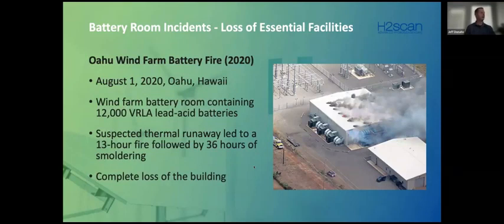Another one was a wind farm in Oahu in 2020. This was a suspected thermal runaway event, and it was a fire that lasted 13 hours, with 36 hours of smoldering, and complete loss of the building. You can see the deflagration vents on top of the building were open, basically channeling that energy out. But of course, in any thermal runaway event with a lead acid battery, you will detect hydrogen, and that could be used as a mitigation plan for that type of incident.